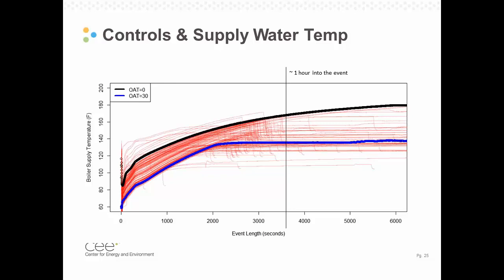The different colored lines represent different outdoor air temperatures. In the case where it's 30 degrees outside, the blue line, there's a call for heat and the boiler kicks on, and slowly ramps from a starting point of about 60 degrees supply water temperature up to its set point around 125, 130 degrees. That ramp up takes about 30 minutes. During that whole ramp up time, we're operating at slightly lower supply water temperatures, and therefore lower return water temperatures and higher efficiencies. When we move to colder temperatures, say 0 degrees shown in the black line, the ramp up takes about an hour and a half to reach its set point of about 170 degrees.